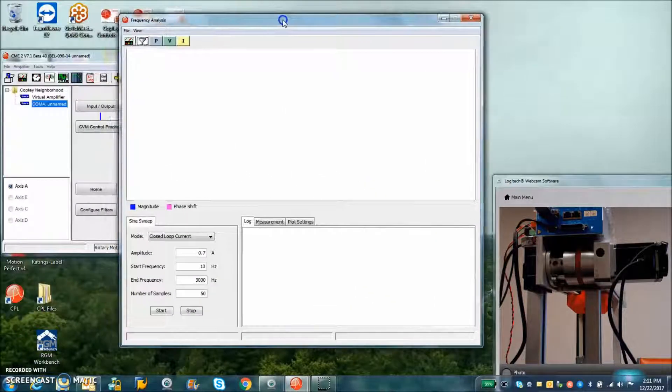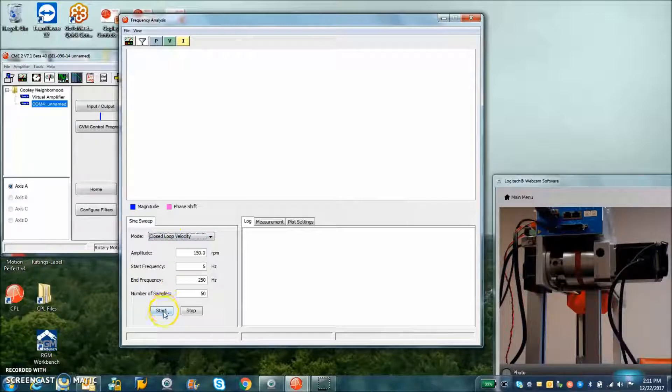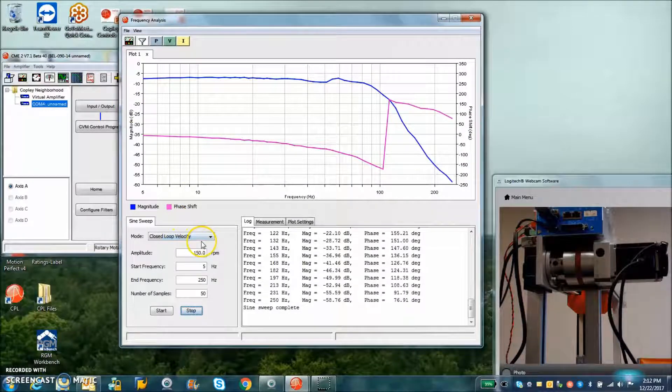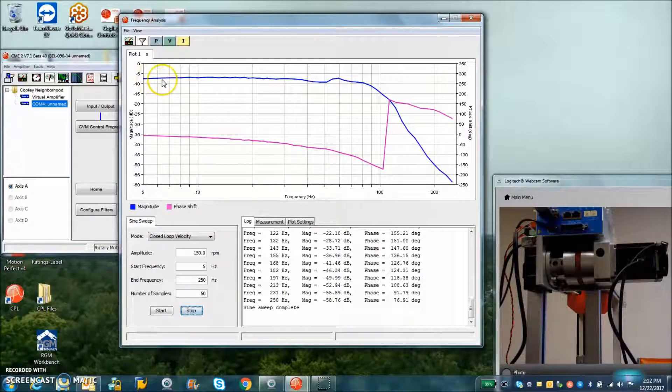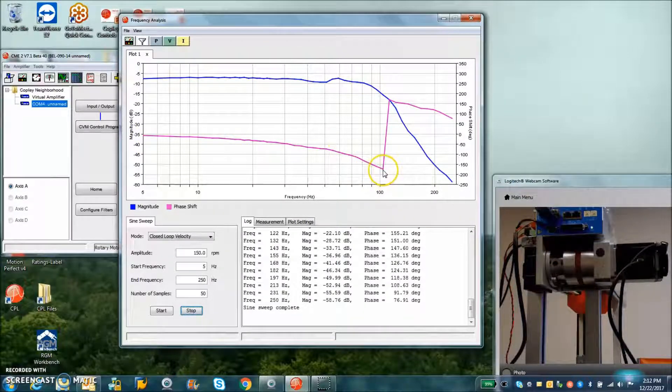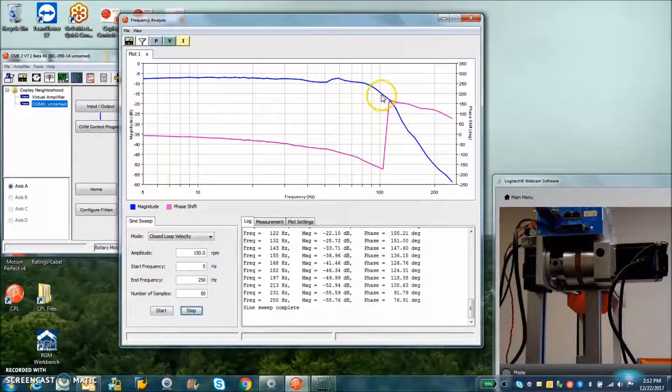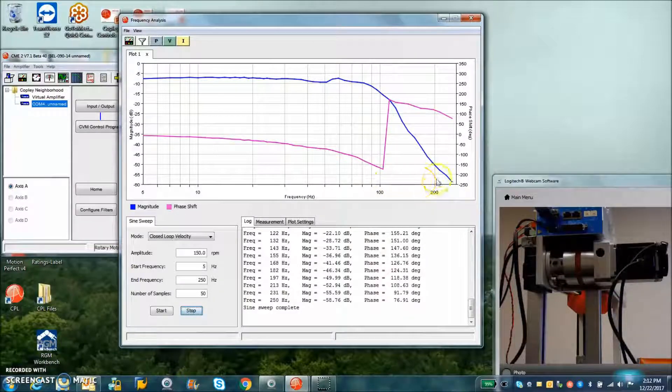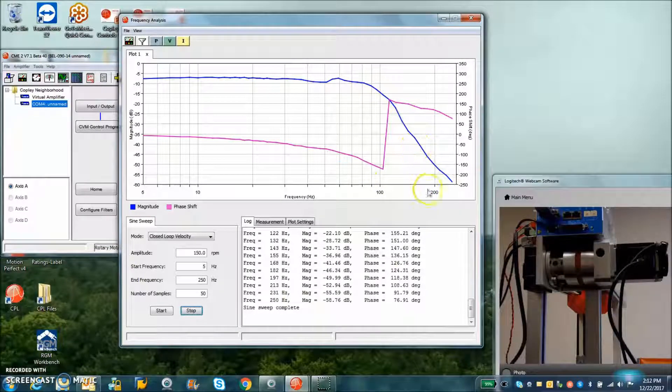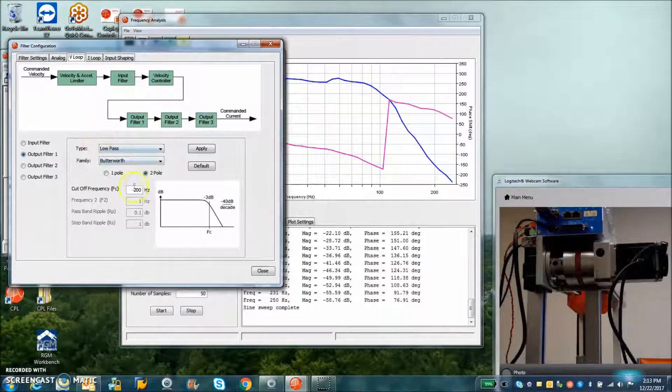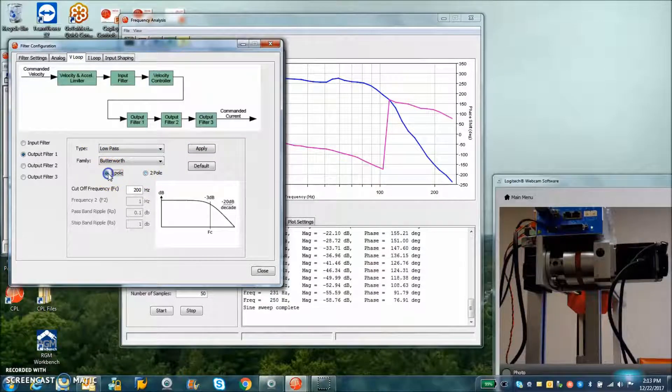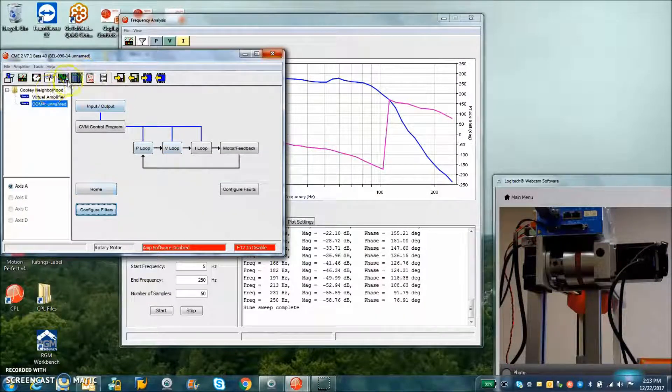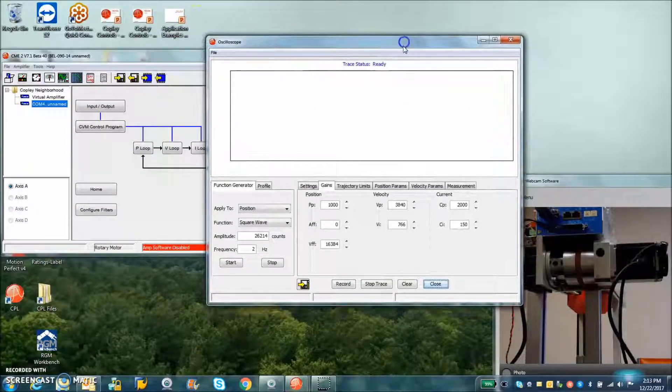So when we do the frequency analysis on the closed loop, this is the closed loop velocity sweep. Goes out pretty flat and rolls off, starting at phase zero. I got a 180 phase shift here at about a hundred and something Hertz and I'm down 15 decibels. So no oscillations. There's a little blip here around 50, 60 Hertz. We'll investigate that further, but you start rolling off just before 200 Hertz. This is explained by the pole at the output of the velocity loop. It's a two pole. We can switch it to a single pole and that'll move out. So we're going to take a look at the tuning of the velocity loop in the normal way now.